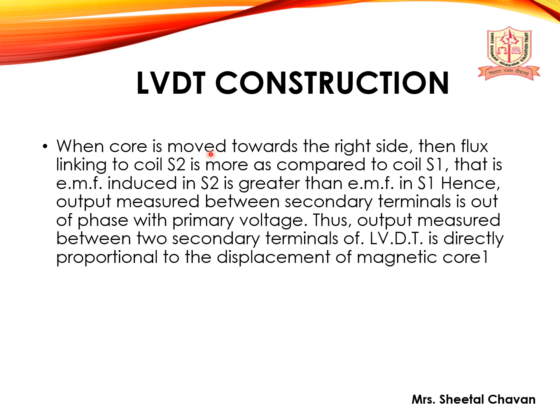When the core is moved towards the right side, the flux linking to coil S2 is more compared to coil S1. That is, the EMF induced in S2 is greater than the EMF in S1. Hence, the output measured between the secondary terminals is out of phase with the primary voltage. Thus, the output measured between the two secondary terminals of the LVDT is directly proportional to the displacement of the magnetic core.